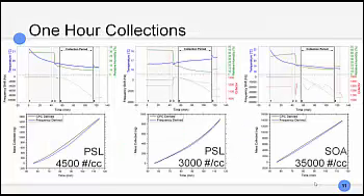So we did a few different tests, and I'm not going to go into too much detail about each of these, but the basic idea I want to highlight is we can test different types of aerosol, so the solid and the liquid particles, and different concentrations. So relatively low, 3,000 particles, and then quite high at 35,000 particles per cubic centimeter.